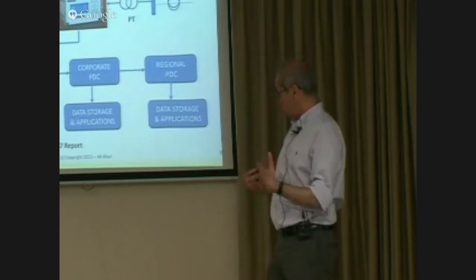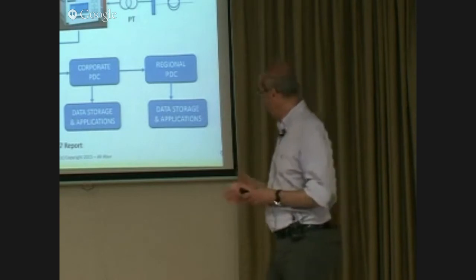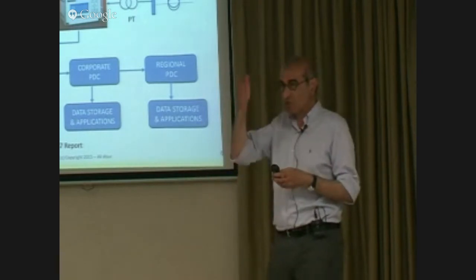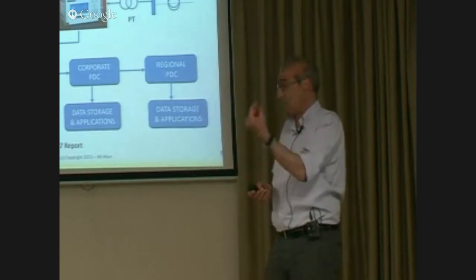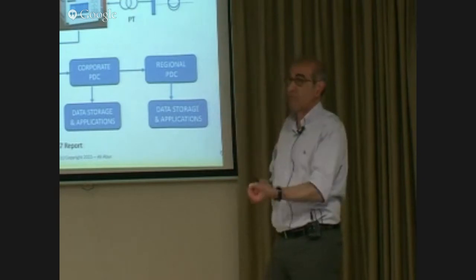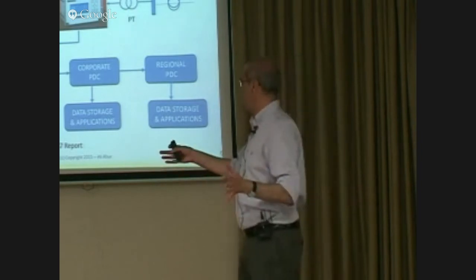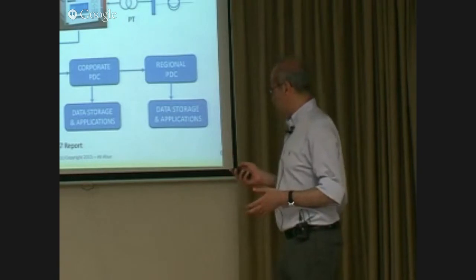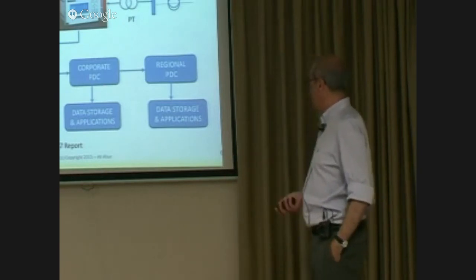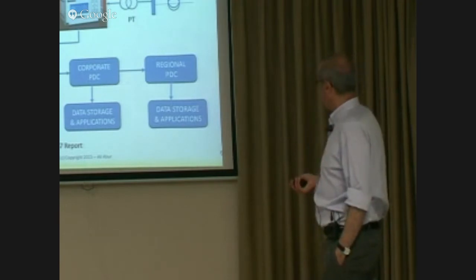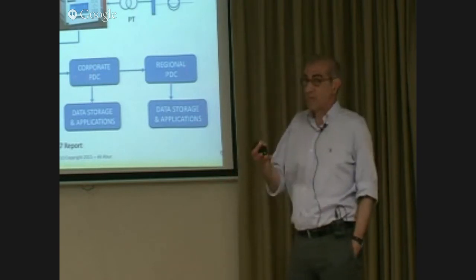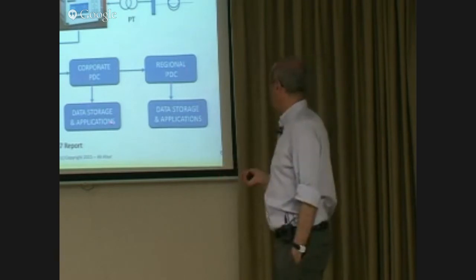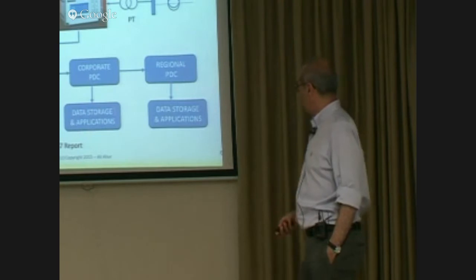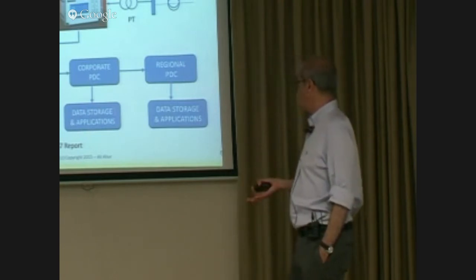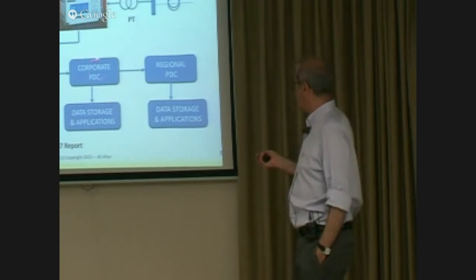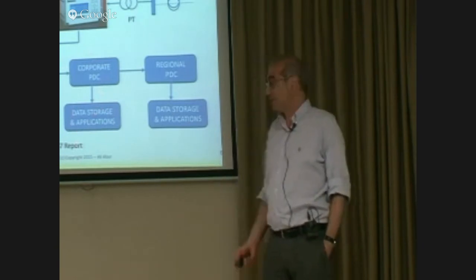But essentially, you get a lot of samples collected by different PMUs, and the job of the PDC is to time-align them, picking up the timestamps which correspond to the same time instant, aligning those measurements, and putting them together in a fashion which is easily distributed or broadcast. If you want to do it in a corporate setting, you may have a corporate PDC; in a regional setting, you can do it similarly. They can also be used for engineering, planning, or other applications - so it could be a background scheme to keep them in a data storage facility, used immediately or stored for engineering studies or applications.